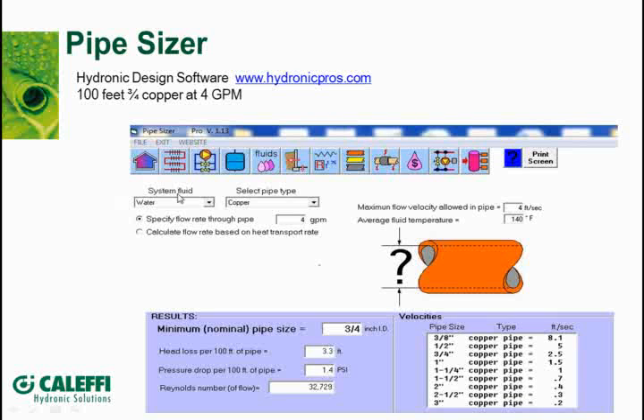So I put a little example here of a system that we're filling up with just basic water. It's copper pipe, 4 gallons a minute flow rate through it. You can even put the temperature of the water, because the temperature is going to make a difference. And you can see what's going to happen here now down in this table with 3/4 pipe flowing 4 gallons a minute of water through it.